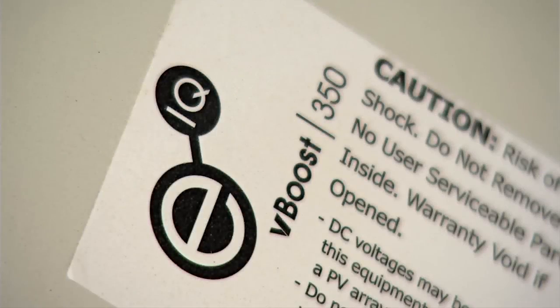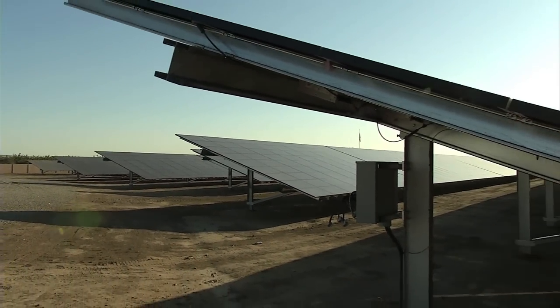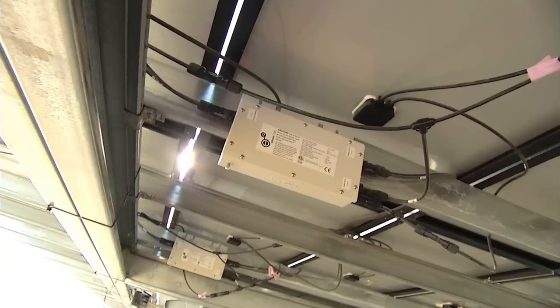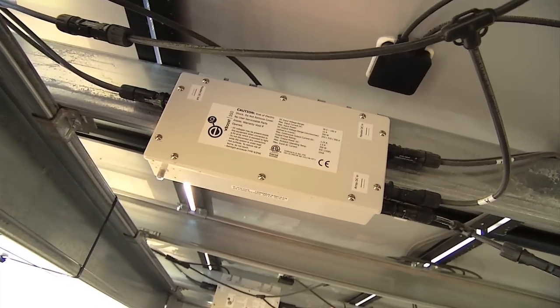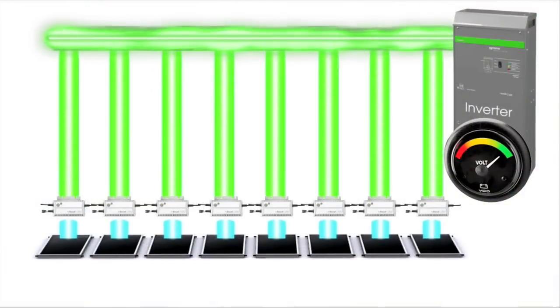EIQ's VBoost technology changes all of this by enabling parallel architecture, which resolves these design limitations. The VBoost module takes the voltage from the module and matches it to what the inverter wants by boosting it to a constant DC voltage. Each module becomes its own independent contributor to the array's power bus.